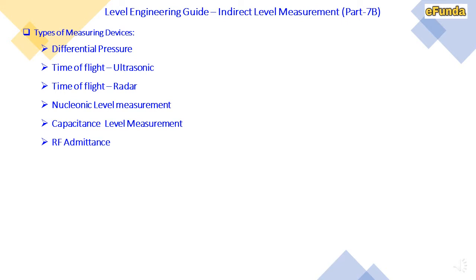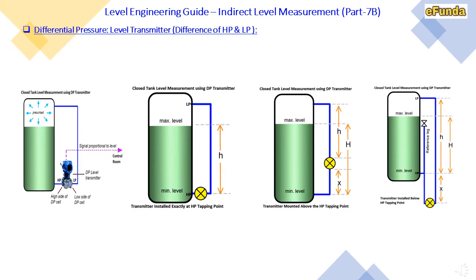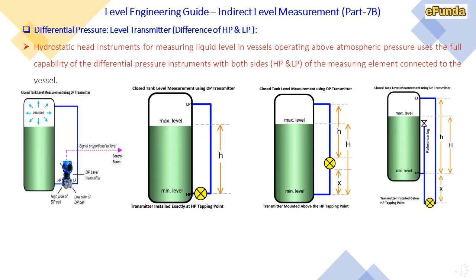We will see the key and most popular application devices used in industry. Our first type is the differential pressure (DP) level transmitter, which measures the difference between HP (high pressure) and LP (low pressure). The differential pressure acts between the two pressures appearing at the HP side and LP side. This technique is used to measure the exact level of liquid inside a vessel — a hydrostatic head instrument for measuring liquid level in a vessel operating above atmospheric pressure, using the full capability of the DP instrument with HP and LP sides connected to the vessel.